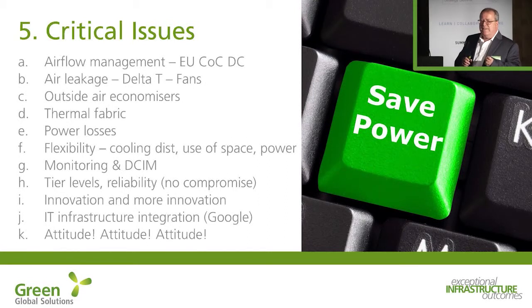That's flexibility. So if I've got 40 kilowatts in one rack, an area with a bunch of supercomputers, but it only happens to be in one or two racks, and the rest of the racks around it might be 3 kilowatts, well, I can handle that under this arrangement. So again, it all comes down to flexibility.